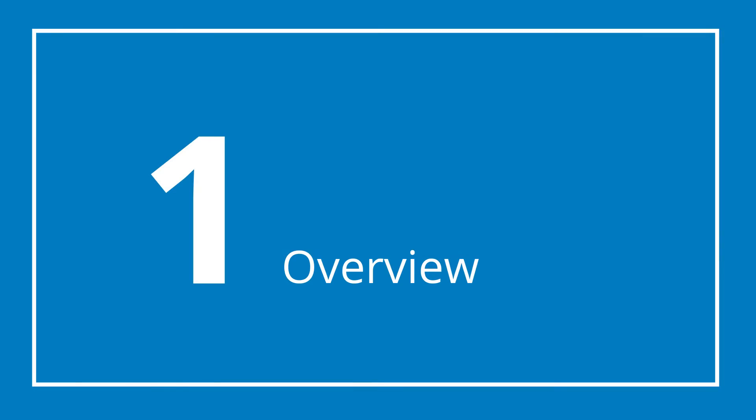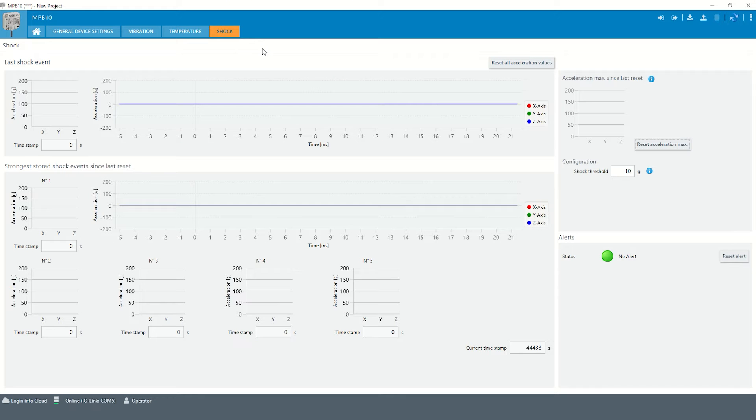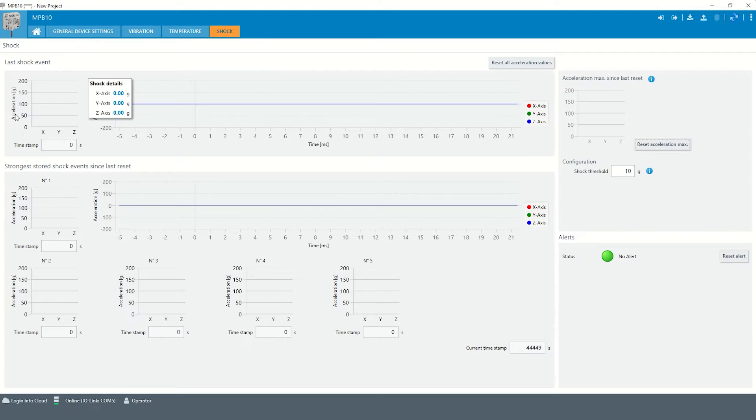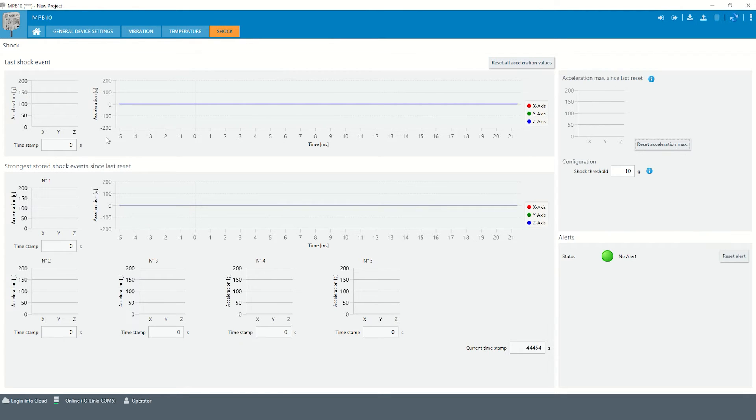Chapter 1: Overview. Besides vibration monitoring, the Multiphysics Box 10 also supports the monitoring of shock events, which is based on the maximum acceleration of the three axes x, y, and z in a measuring range of plus minus 200 g.